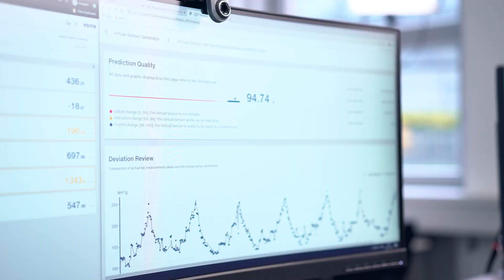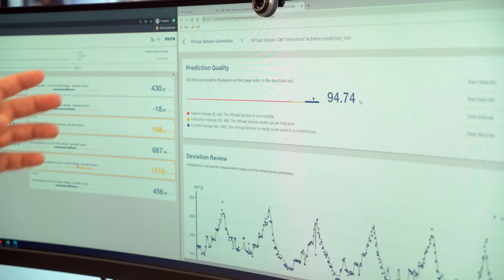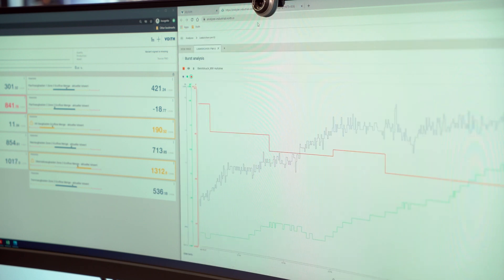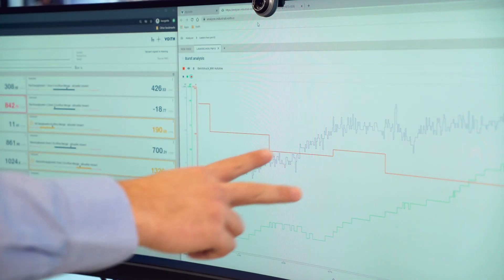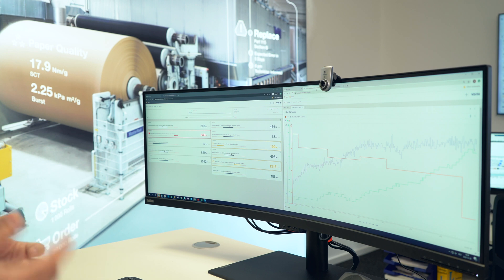In Lakirchen, we used our virtual sensor builder. With this tool, we are able to analyze the phenomena and find the root causes. In this case, we identified two signals: the enzyme flow rate and the retention aid post-elution. And check this out — when we saw that the burst values dropped, we saw those two signals increasing. Therefore, we communicated with Mr. Dirkus Leifeld and explained the correlation between burst values, the enzyme flow rate and the retention aid post-elution.